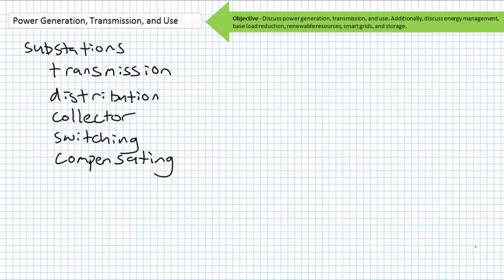A switching substation is something that redirects power from one region to another, or vice versa. This is accomplished via switchgear and something called a phase shift transformer, which maintains voltage at the same magnitude but changes one region's voltage phase shift with respect to another. This affects the direction in which power flows.